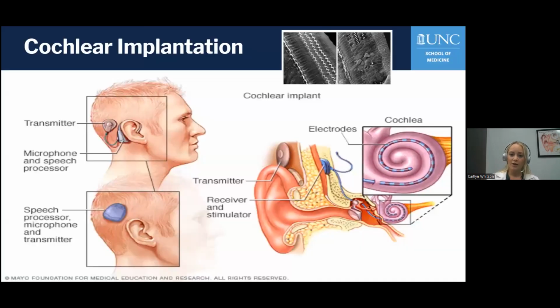So a cochlear implant looks kind of like a hearing aid on the outside, but it has this coil transmitter that attaches to another part under the skin. So there are two pieces, the external and the internal. The external has your microphone that's picking up the sound. It has a power supply with a battery and a sound processor, sends the sound to the transmitter, which goes through the skin to a magnet on the other side. So this transmitter on the outside is removable. You take it off, you don't hear. You put it on its magnet, you can hear.